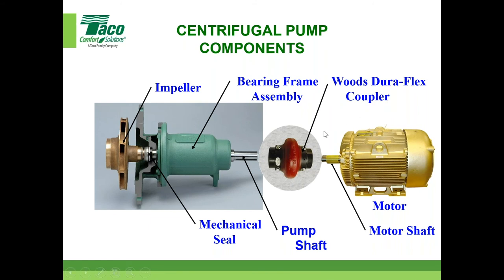And then one last question, Brett, for this category. In what cases should you use packing seals instead of mechanical seals? For most HVAC hydronic applications, I would stay away from packing seals. But Rich, do you have any advice on that? Maybe for real, actually dirty. We touched base on this the other day when it came to the vertical turbines. That's a different pump. In our standard base-mounted pump and vertical inline pumps, they have mechanical seals. We do not offer a packing seal.